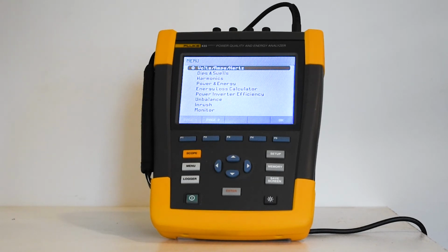Default values are available for the nameplate settings and ranges. Use F1, Unit Setup, to open the setup screen to configure these values. The selection depends upon the default motor frequency. The function keys guide the user through the screen setups. Press F1 and select the Unit Setup screen to open the Motor Analyzer Function Preference screen. This permits the user to select metric or imperial units for the mechanical motor power, torque, and default motor frequency.